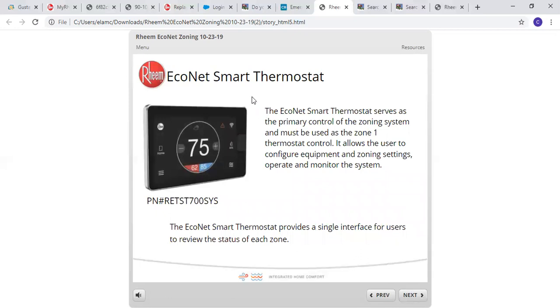The heart of the system is going to be the Econet smart thermostat. The smart thermostat is going to serve as your primary control of the zone system, and it must be used as the Zone 1 thermostat. It will allow the users to configure equipment, zoning settings, operate, and monitor the system. It is important. The part number here is the RET-ST700SYS. This thermostat is what you have to use for the primary Zone 1 thermostat.